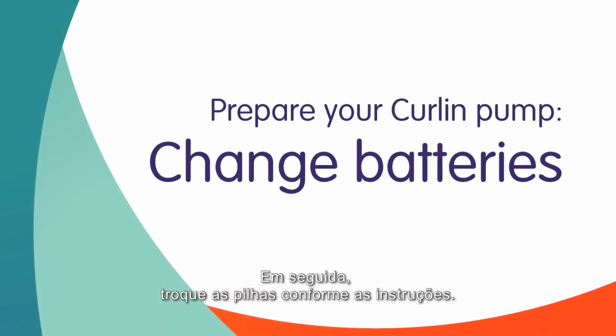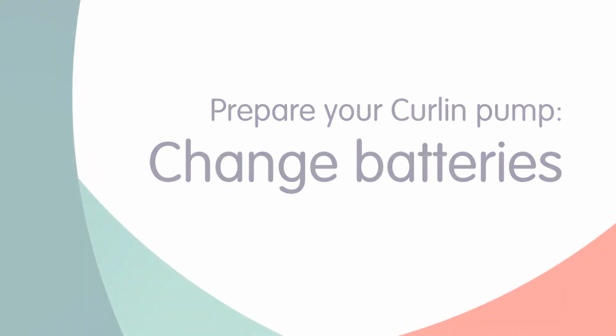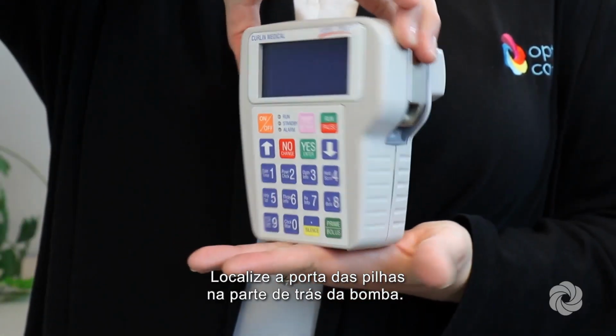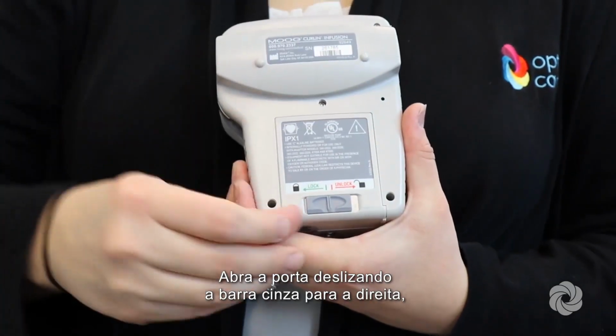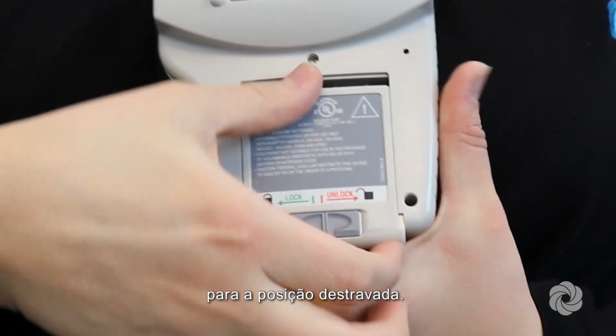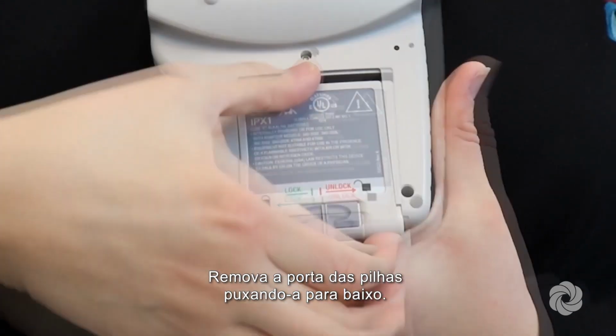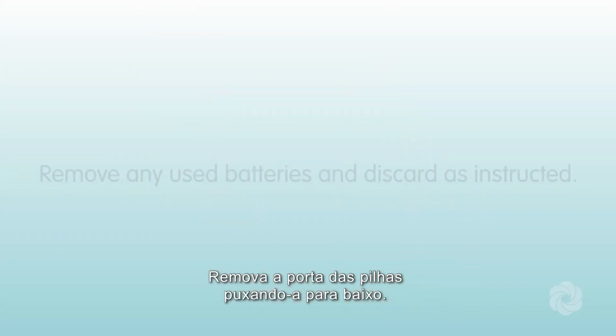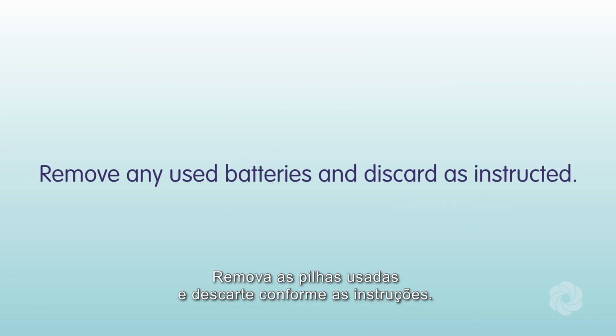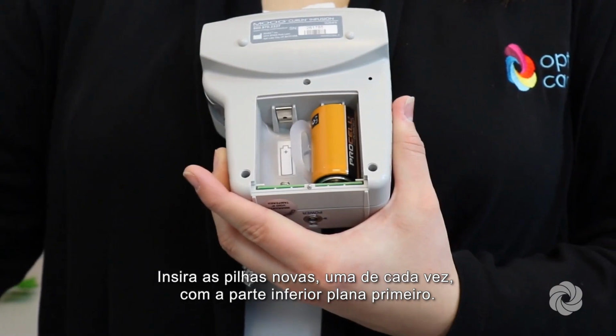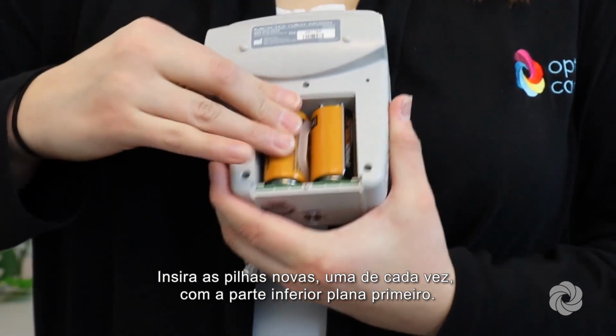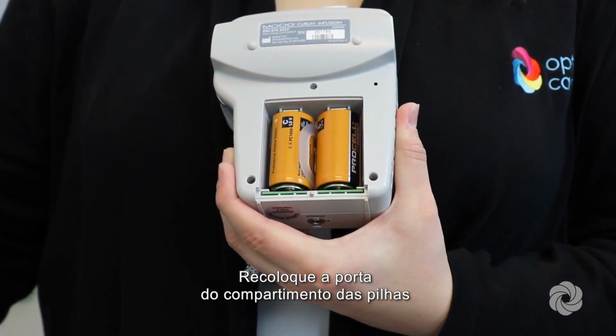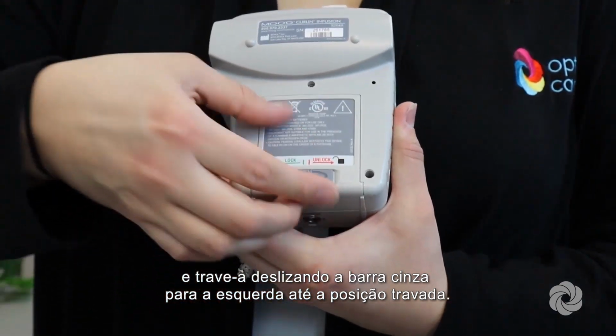Next, change the batteries as directed. Locate the battery door on the back of the pump. Open the door by sliding the gray bar right to the unlock position. Remove the battery door by pulling the door downward. Remove the used batteries and discard as instructed. Insert the new batteries one at a time, flat bottom side first. Replace the battery compartment door and lock by sliding the gray bar left to the lock position.